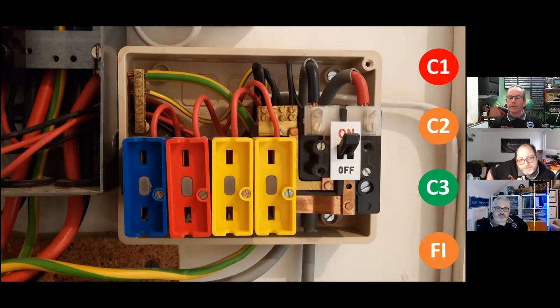The other thing here is these 20 amp rewirable fuses, because of that correction factor of 0.725, you can't have 2.5 millimeter cable on a 20 amp rewirable fuse, but you can on a 20 amp circuit breaker. Now, in this particular case, it's a fixed load, so not necessarily a huge issue, but it's another thing to consider. No wonder they sold so many retrofit breakers.